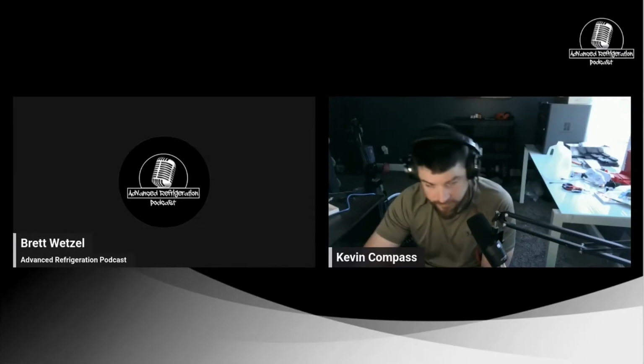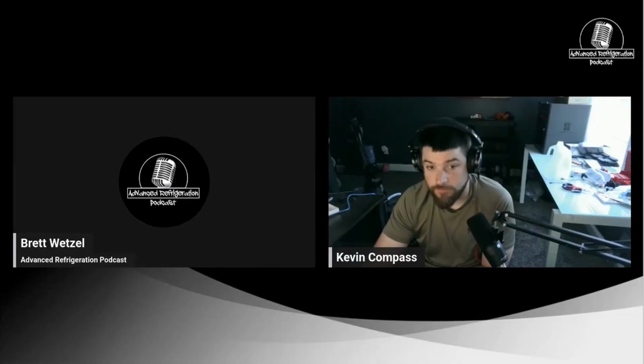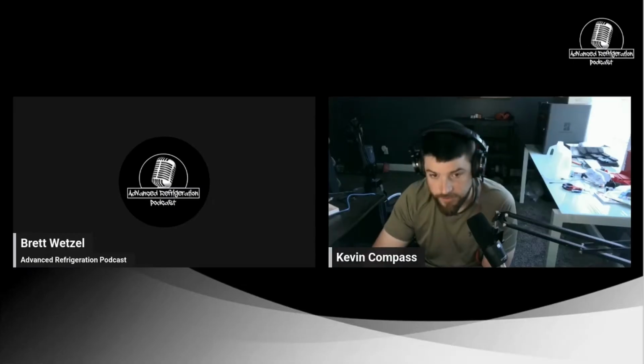A lot of the OEMs are starting to put external strainers on these valves. So you'll have an external, like a Y strainer in front of it. These do plug up, especially if you have a really bad startup or if you're using a lot of TIG welded steel. You're going to be cleaning these. So make sure there's ball valves on both sides before you go to start them, because you don't want to have this down for an extended period.